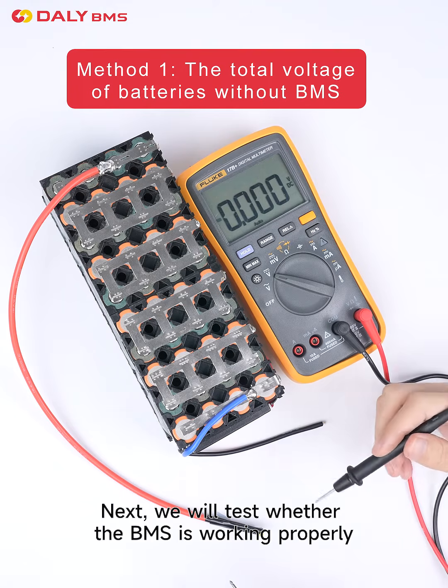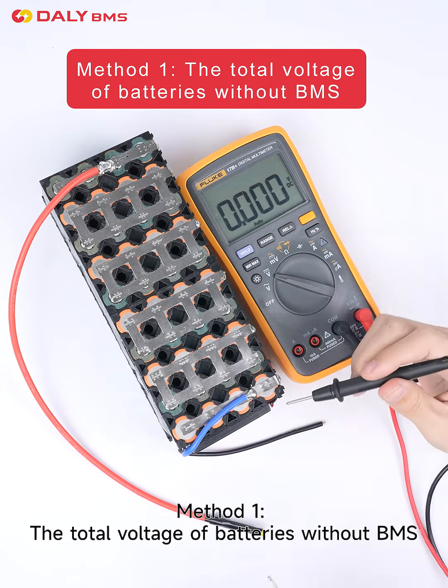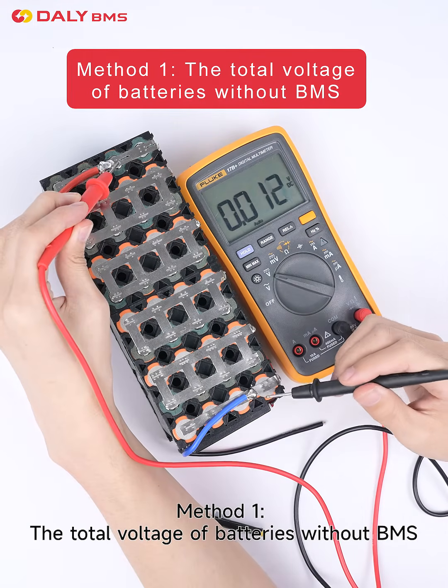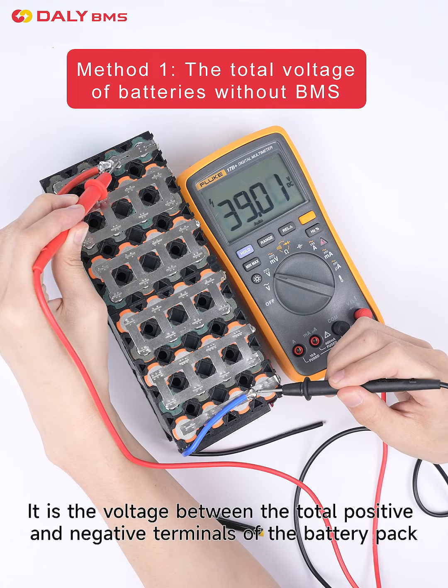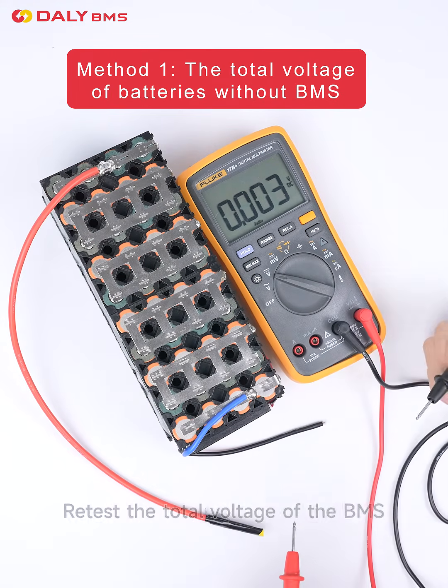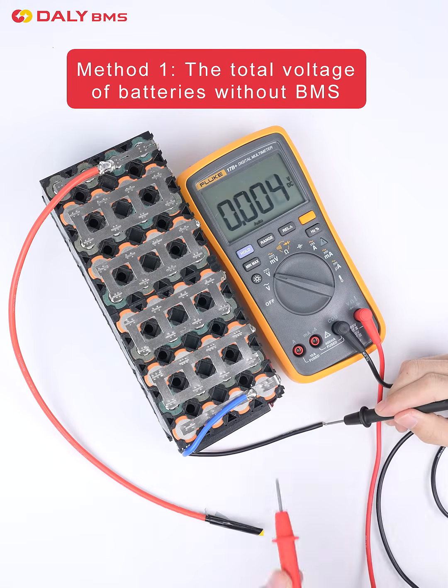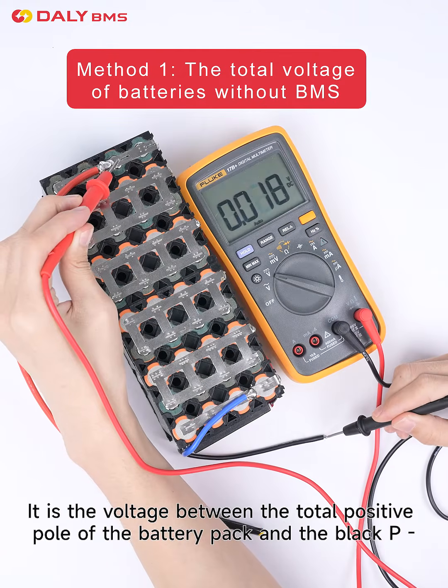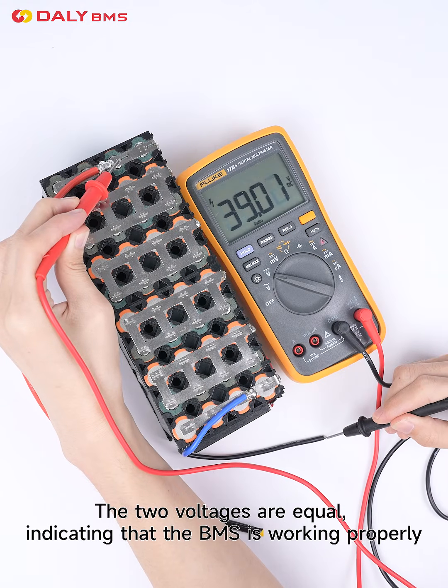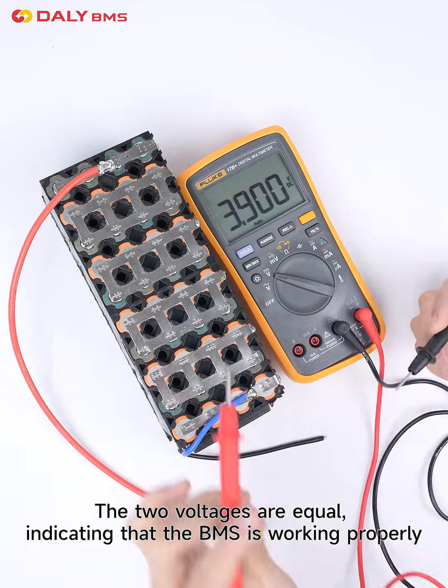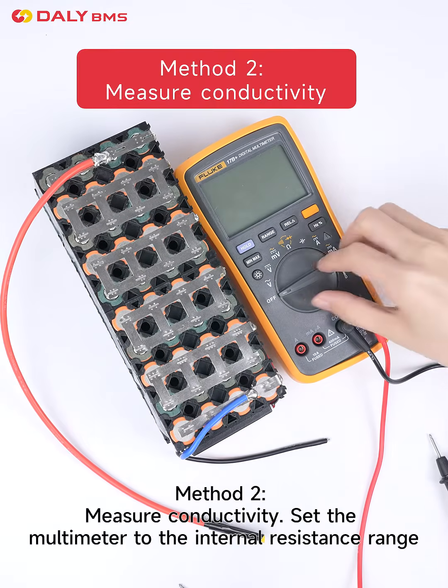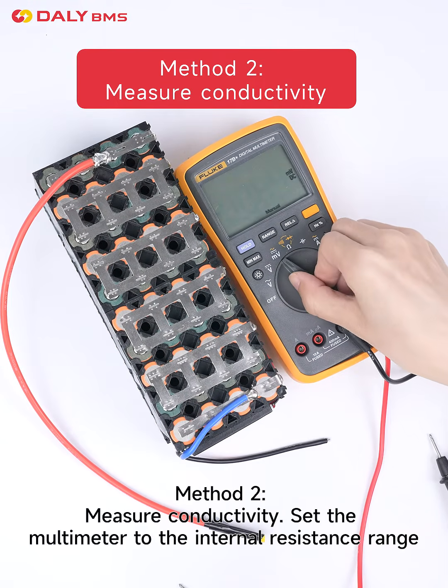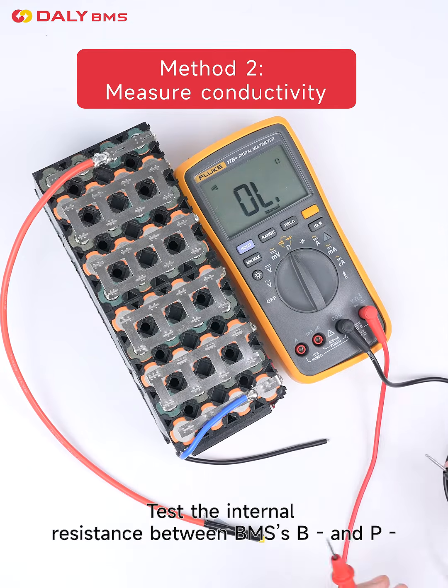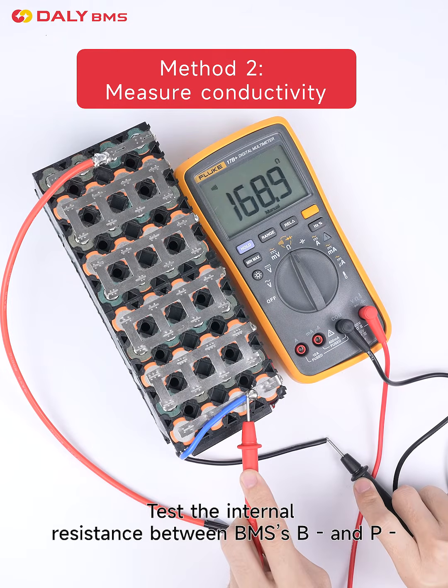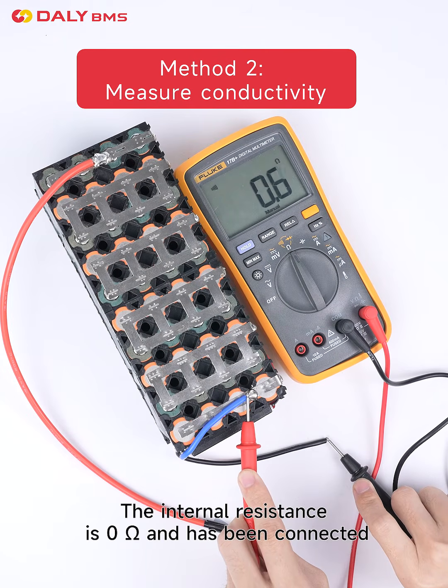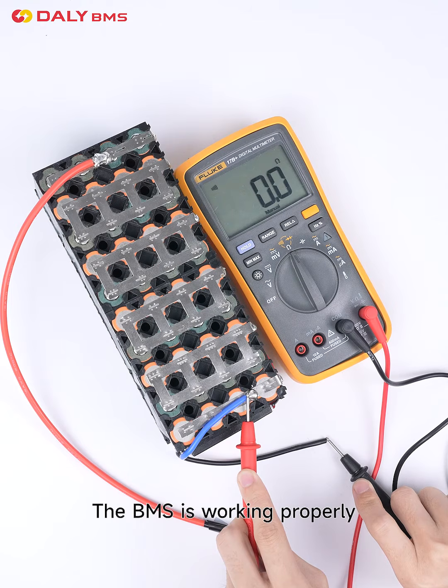Next, we will test whether the BMS is working properly. Method 1. Measure the total voltage of the battery without BMS, which is the voltage between the total positive and negative terminals of the battery pack. Retest the total voltage with the BMS, which is the voltage between the total positive pole of the battery pack and the black P wire. The 2 voltages are equal, indicating that the BMS is working properly. Method 2. Measure conductivity. Set the multimeter to the internal resistance range. Test the internal resistance between BMS's B- and P-. The internal resistance is 0 ohms and has been connected. The BMS is working properly.